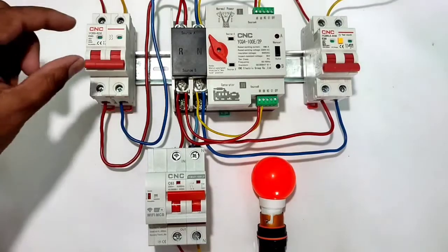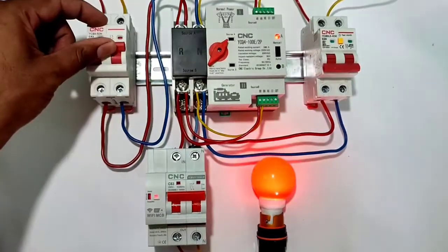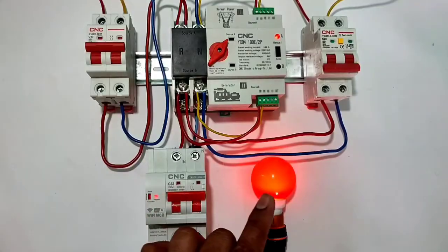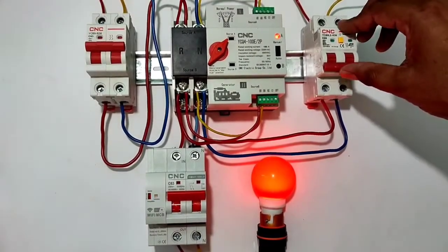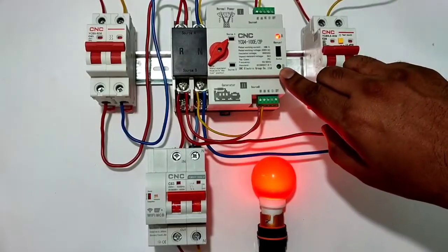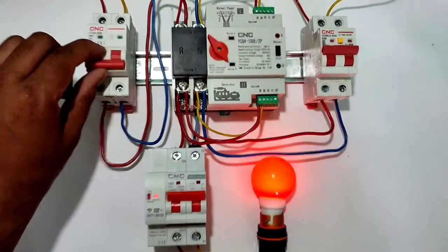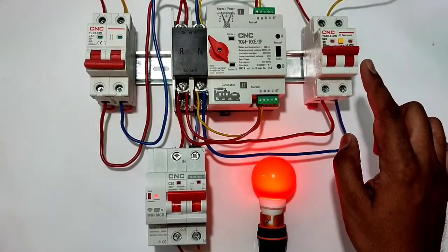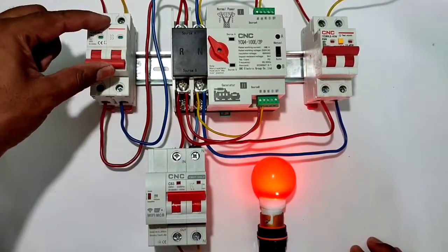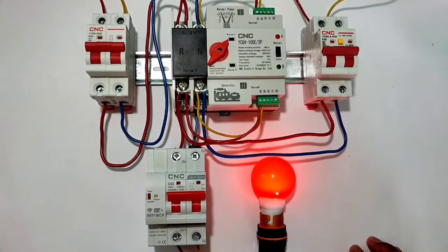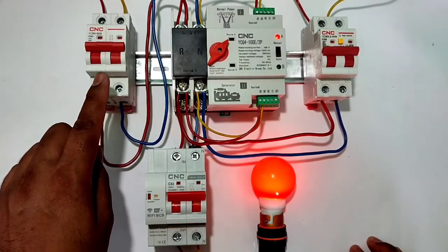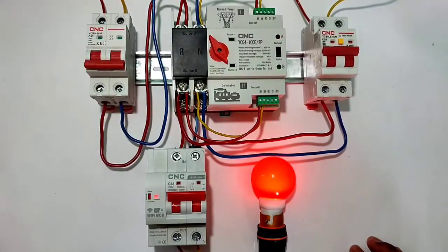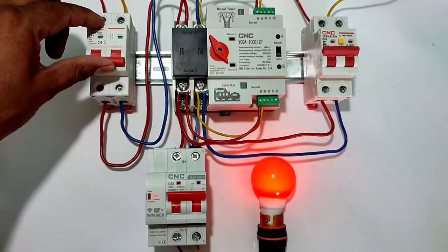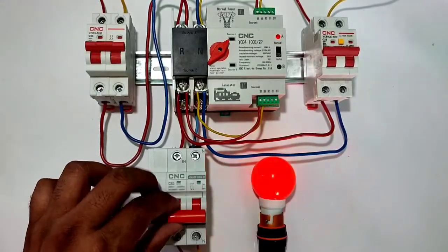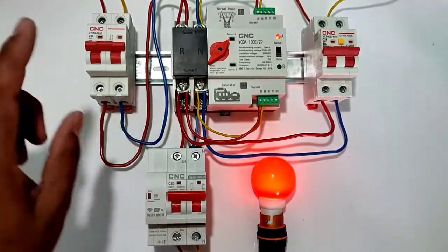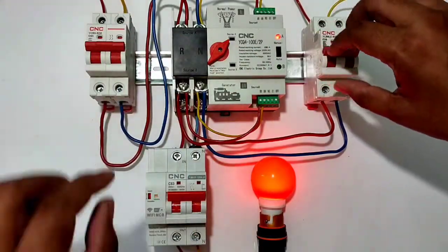Now let's see the working of this automatic transfer switch. Okay, if your main power supply is on, your load always runs on the main power supply. Okay, now we start the secondary power supply, the generator. Now you can see here both indicators are glowing. Okay, if your main power supply stops, your load automatically transfers to the generator power supply. If the main power supply comes back, your load automatically transfers to the main power supply. So you can see here your load always runs on the main power supply. If the main power supply goes off, your load transfers to the generator power supply. If your main power supply comes back, your load transfers to the main power supply.